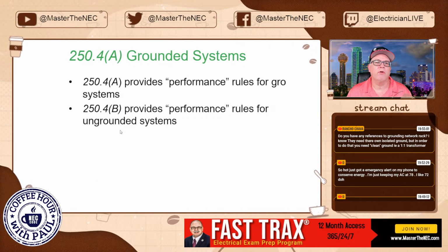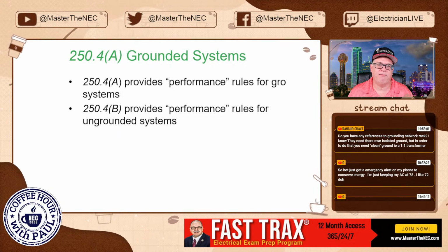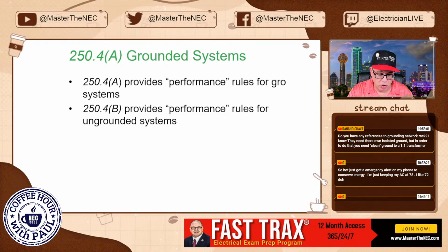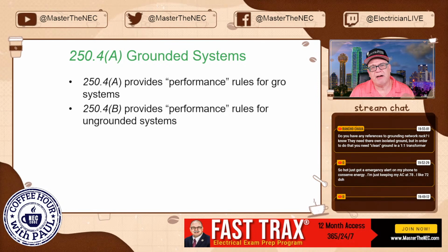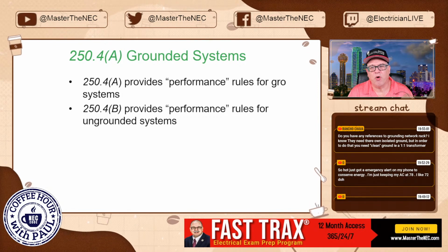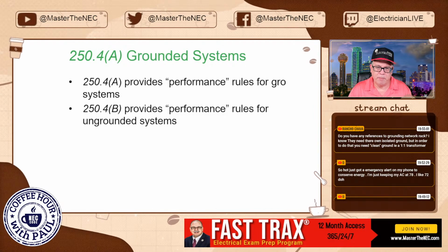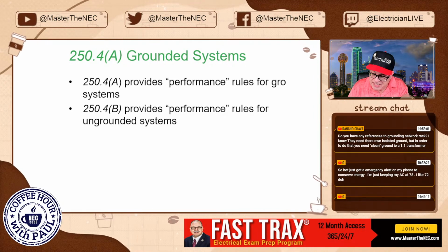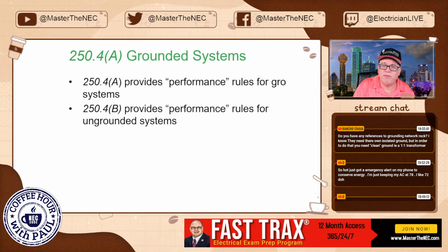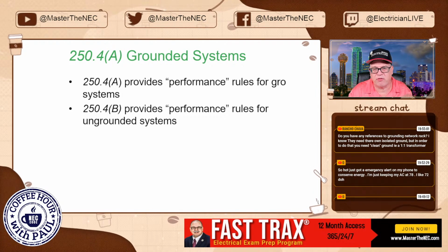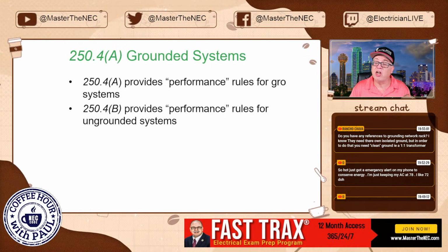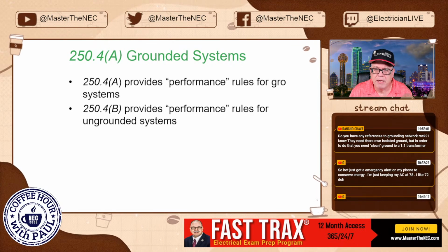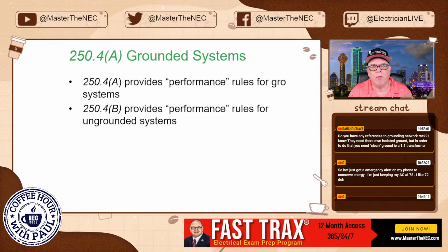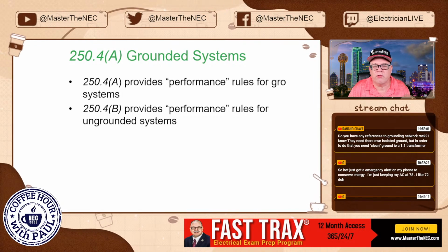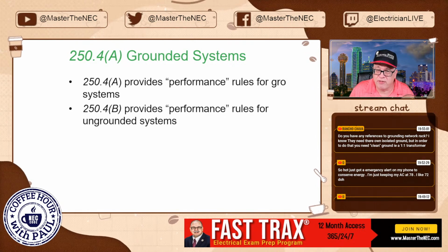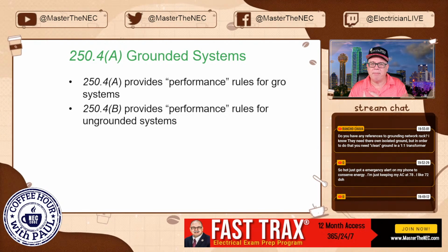All right. 250.4(A), grounded systems, and hopefully you're following along in your code book if you have it handy. 250.4(A) grounded systems provides performance rules for grounded systems. So if you have a grounded system intentionally connected to earth, then 250.4(A) is going to give us some performance requirements. And if you have an ungrounded system, then 250.4(B) has performance rules that you have to follow for ungrounded systems. Okay, so kind of keep that in mind.